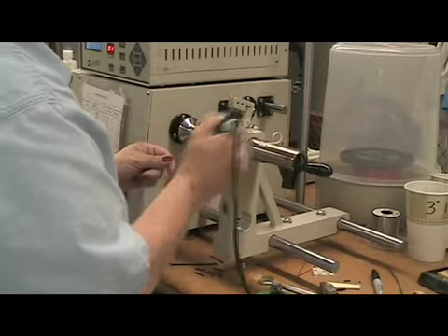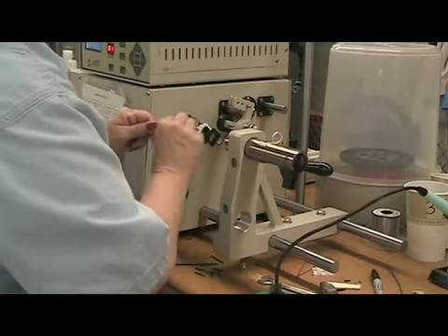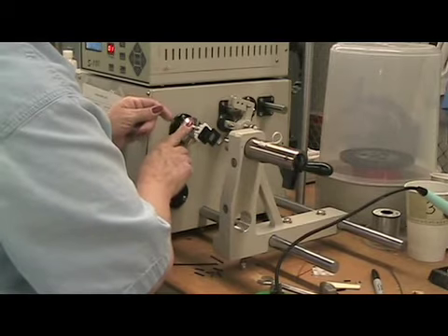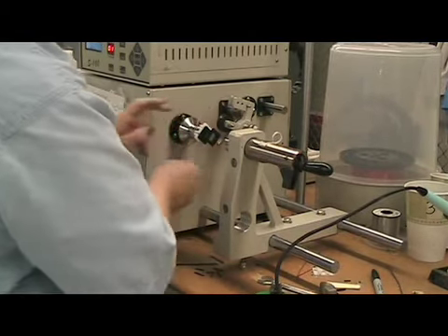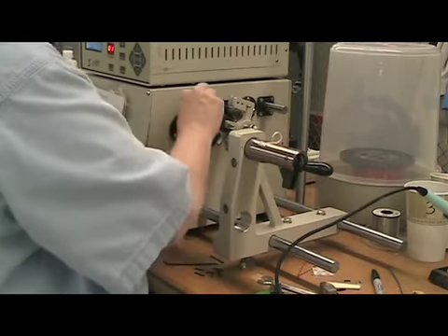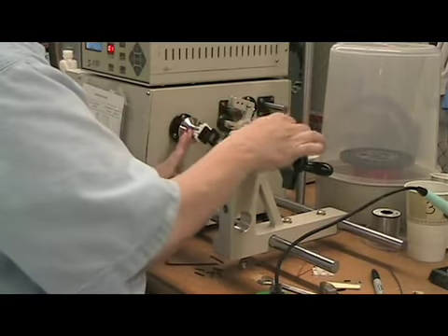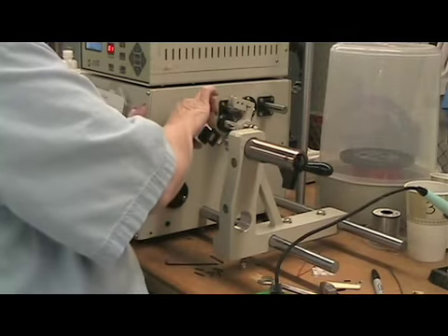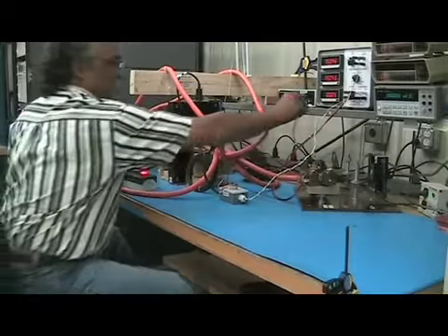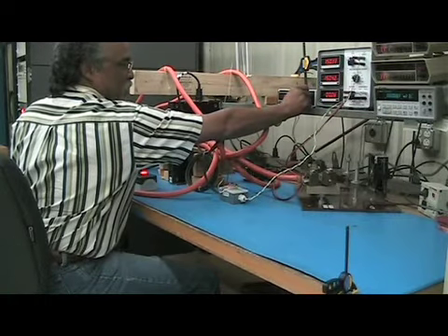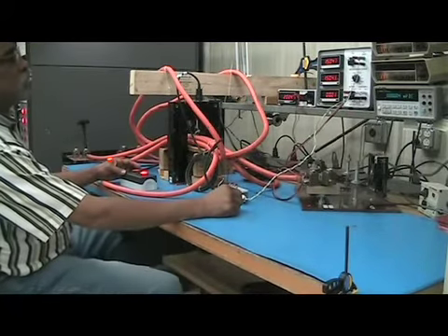It requires some electronics to drive it, and there's a cost associated with that more sophisticated electronics. On the positive side, you get greater linearity, you have better temperature stability of your output, and in some cases, because of the transformer action, even better higher frequency response. So you gain those advantages at the expense of it being a somewhat more expensive transducer.